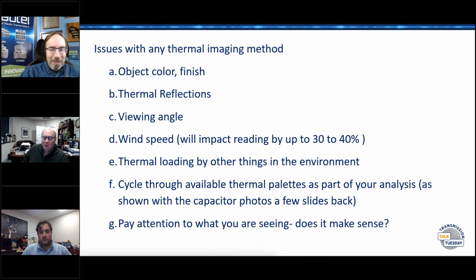It's just, again, how well an object tells you its temperature depends on the color of it, its finish, the material, and anything reflecting onto it. The angle matters too, if you look at it from too sharp of an angle, it'll lie to you about the temperature. Wind speed can cause a 30 to 40% difference. Thermal loading, I mentioned, if you have an air conditioner that turns on and off. Rafael was on the job site and sent me a shot, I said look at this, it's hot. I said yeah, look beyond it, there's a heating unit exhaust blowing on the device. So that's the kind of thing, you look for what else could be loading your device. Are you near a heater? Well of course the thing next to it will be hot. But the big one: take a look at it, does it make sense? Does it make sense that the thing you're looking at should be hot? Is it the environment, is it just normal? What's normal for that piece of equipment?